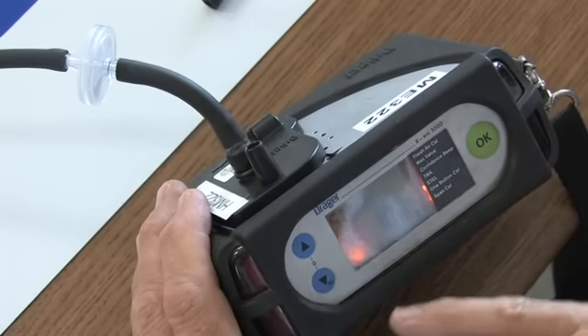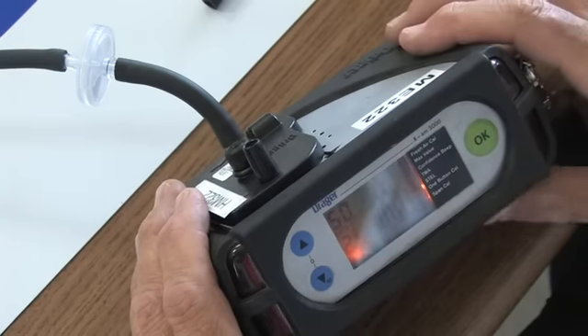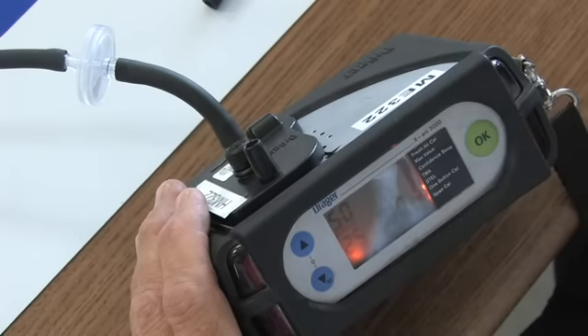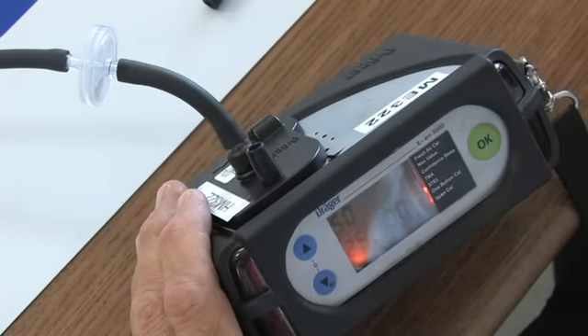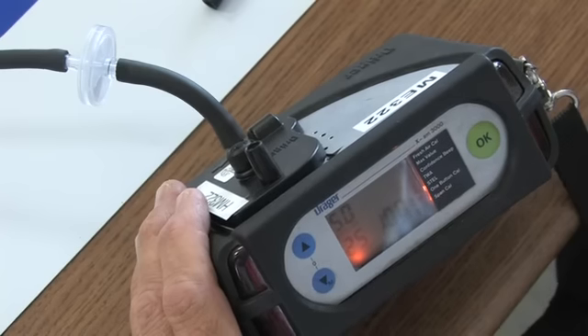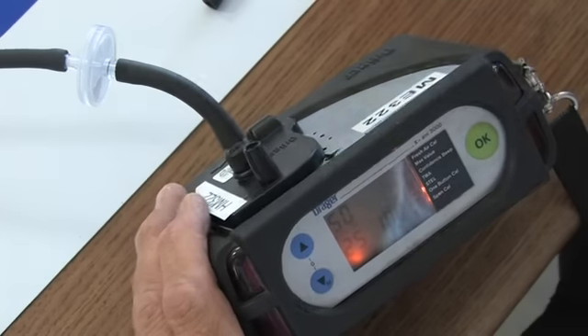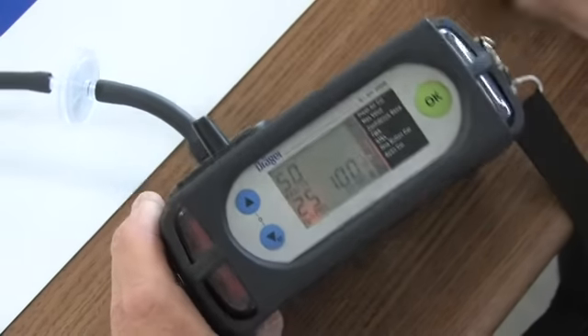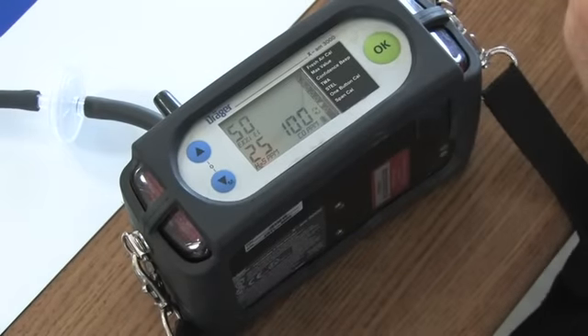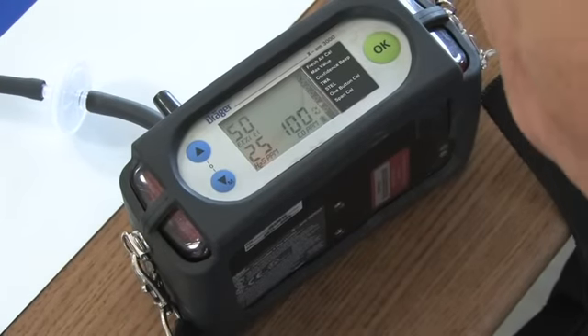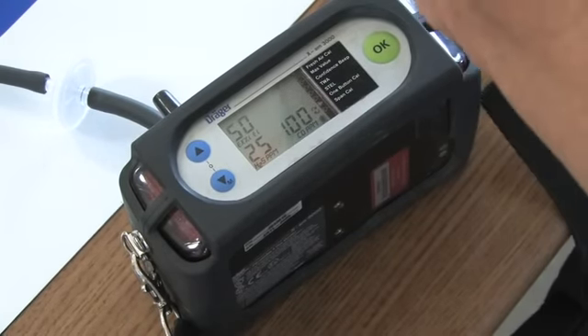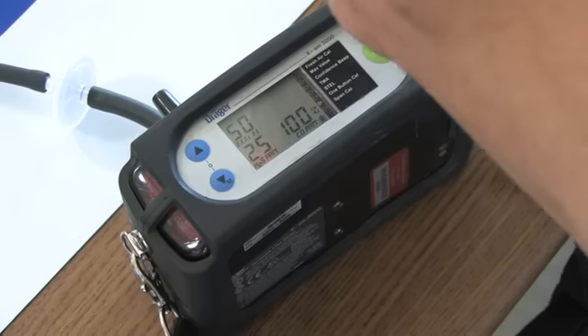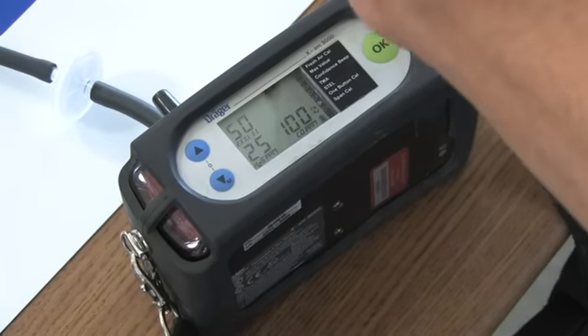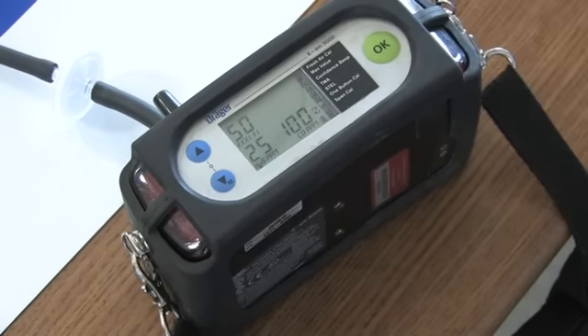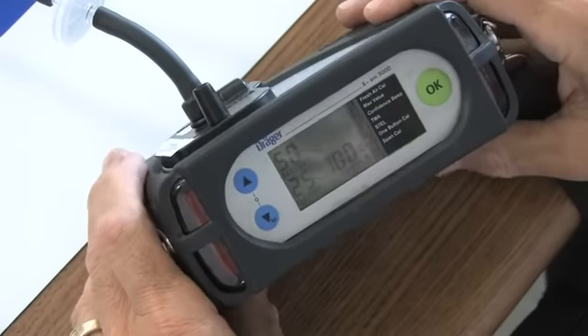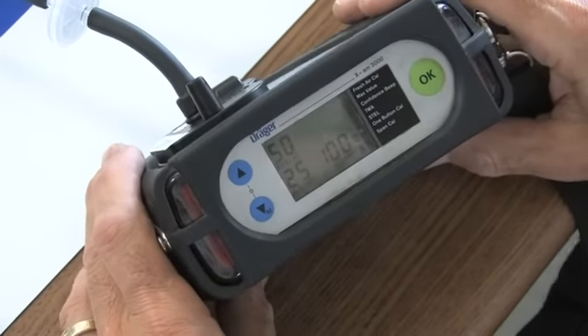Now, here are the numbers that the instrument is expecting. Notice that the oxygen is removed because when you do a fresh air cal, that's your calibration for oxygen. You do not have to blanket this with nitrogen to drive it to 0. So I'm going to hook up my gas. You don't touch anything. All you do is hook the gas up while the numbers are sitting there staring at you, and when the instrument starts to detect the gas, it will start making its movements. And here we go.